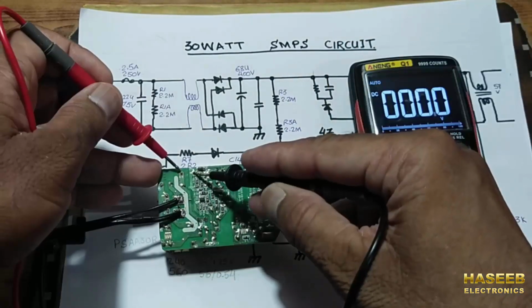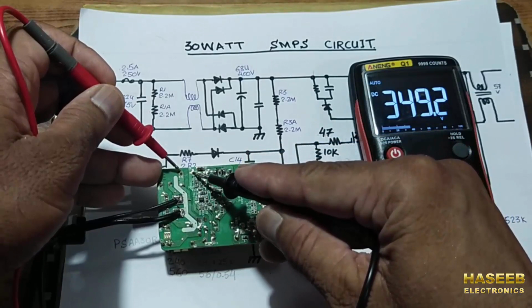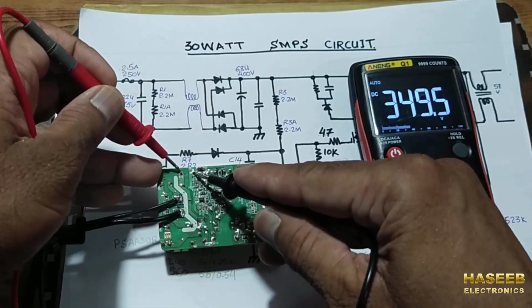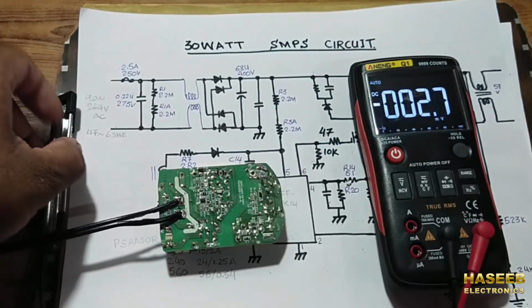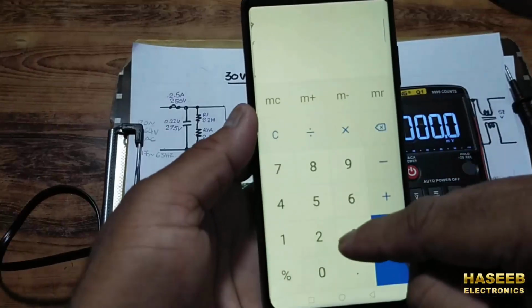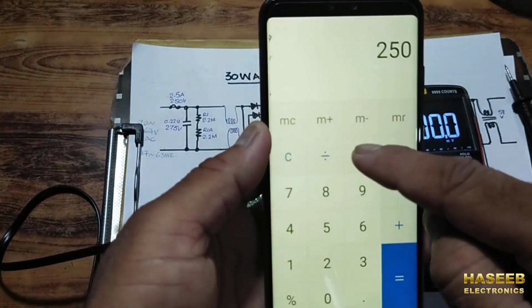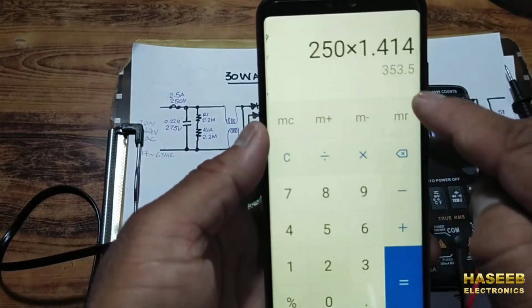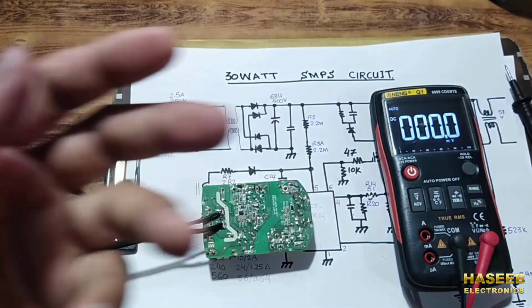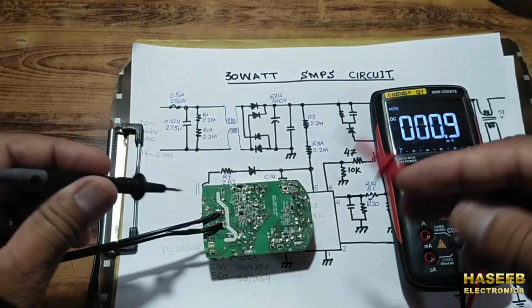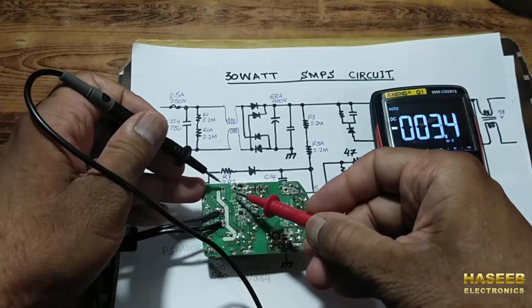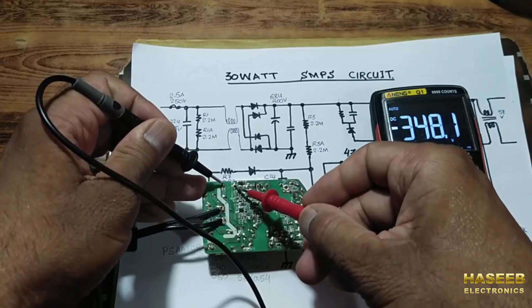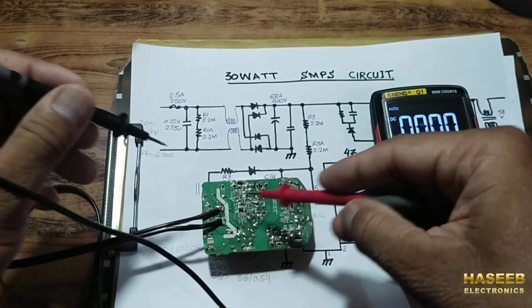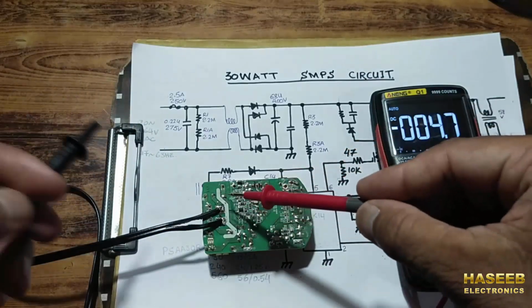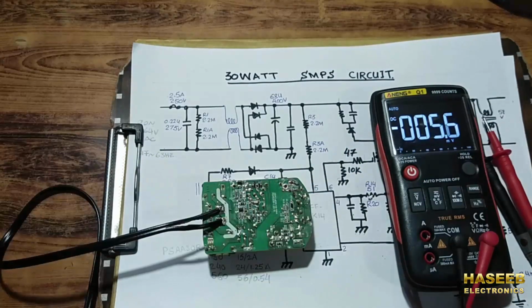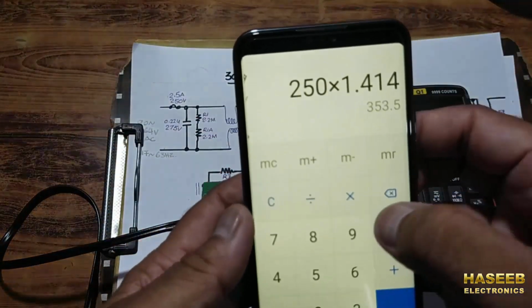The DC voltage I am receiving is 349 volts DC, because this power supply will work from 90 volt to 264 volts. This time I am receiving 250 multiplied by 1.414, which is 353 volts. The DC voltage at the DC capacitor is 348 volt with some load and some ripples, so around 353 volts must be available here.